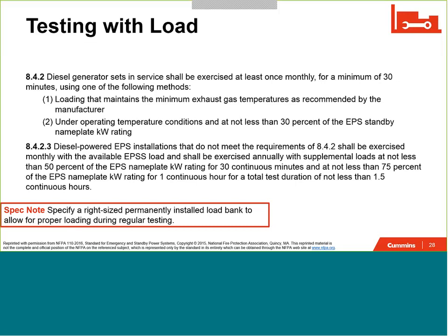Again, I would like to say that most manufacturers within North America are consistent with these testing requirements. However, I would always recommend you yield to the generator manufacturer testing requirements. Those requirements are put in place in order to help you drive your system to be more reliable, and deviating from that may drive towards a less reliable power system. Our recommendation would always be to specify a right-sized, permanently installed load bank to allow for proper testing. Otherwise, you are bringing in load banks on a rental basis, which can actually be more costly than a permanently installed product.